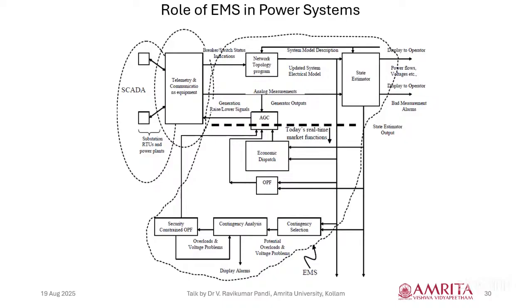Whatever SCADA substation data or remote terminal unit telemeter data comes in, first it goes to the network topology program, and then state estimation is performed. From the state estimation, it is given to economic dispatch, optimal power flow, and AGC control. Then contingency and security-constrained OPF or short circuit analysis are carried out.